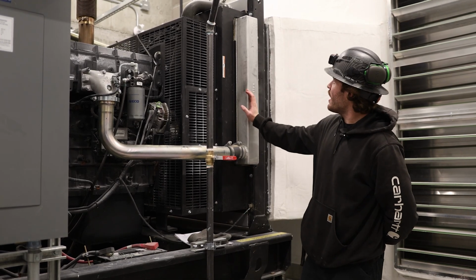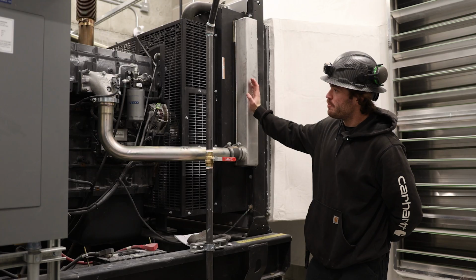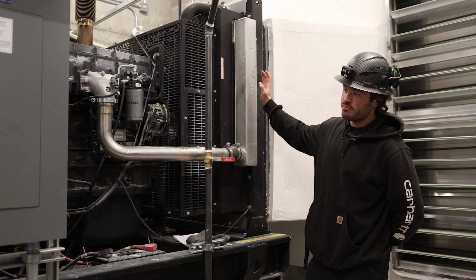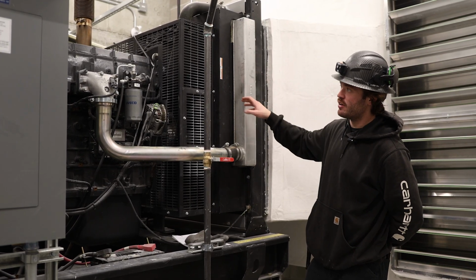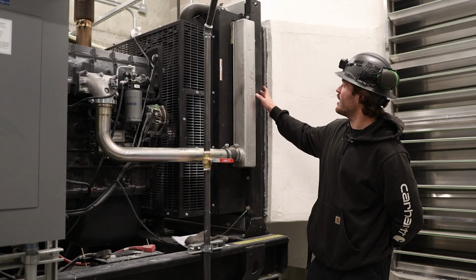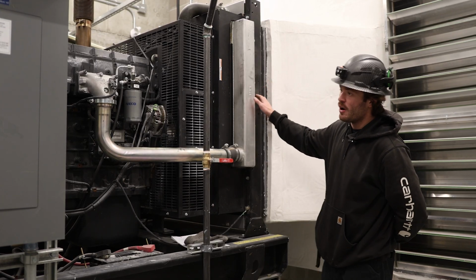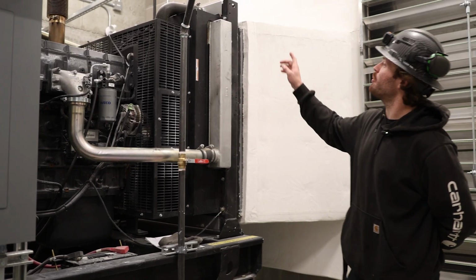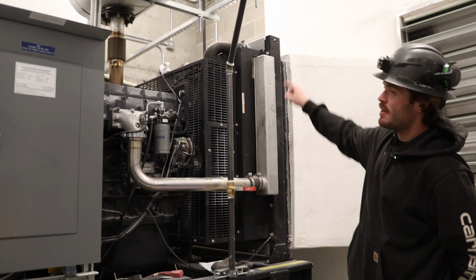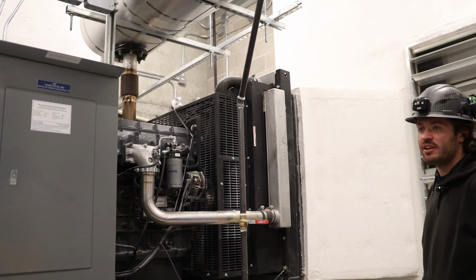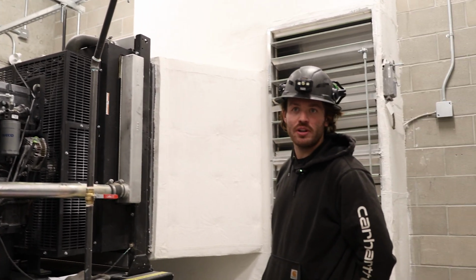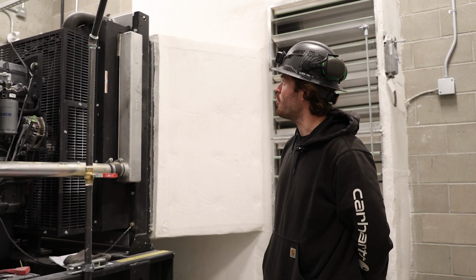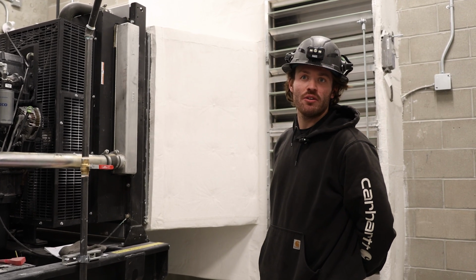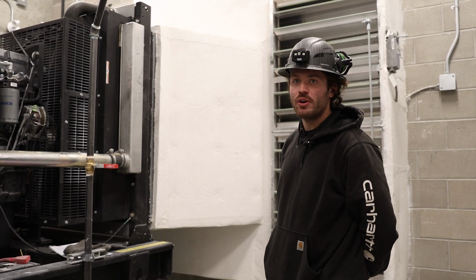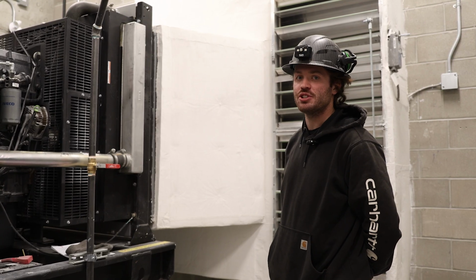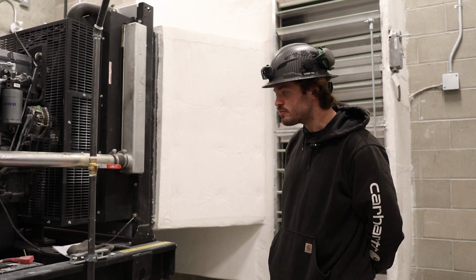Up in the front, we have our charge air cooler. This is our intercooler for our pressurized turbocharged air going into the intake. And in front of that is our engine radiator. Our engine radiator has a cap up at the top in the middle of it, just a standard conventional radiator cap for adding fluid to it if need be. The level is monitored on the radiator, so if our level drops below a certain point, it will throw an alarm and actually shut down the unit itself.